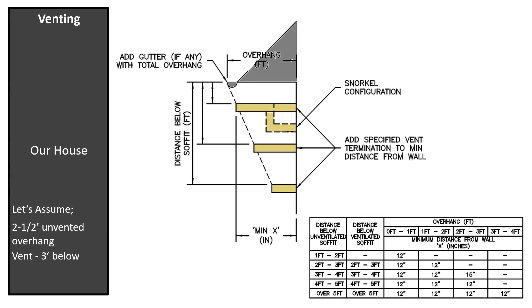Many questions relate to soffits and overhangs. This question is answered in the I&O manual. First, determine how far below the soffit or overhang the vent will be, and how far the soffit or overhang projects from the building. In our example, the soffit is two and a half feet and the vent will be three feet below the unvented soffit or overhang. The vent termination would be 12 inches from the wall.